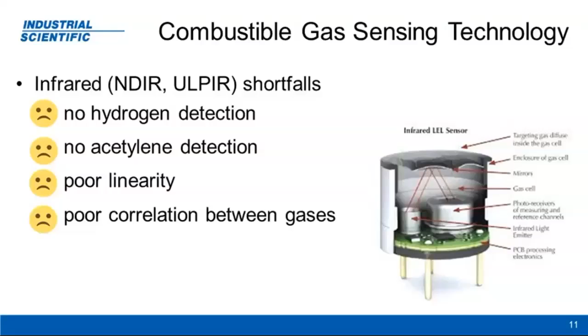Infrared sensors have poor linearity in general. The technology is not inherently linear, and so it has to be compensated for to make it linear. And there's generally a poor correlation between gases, where the outputs of the catalytic bead sensor are linear, and it's very easy to correlate one gas to another, response to another based on what a sensor's calibrated to. The same doesn't apply to the infrared sensors. Very, very poor correlation, and a gas other than what the sensor's characterized to and calibrated to can cause you some problems.